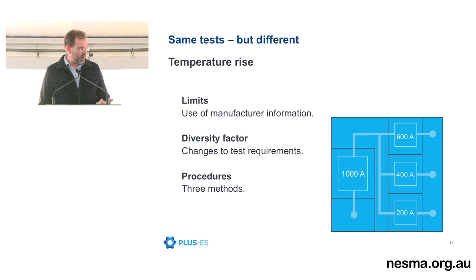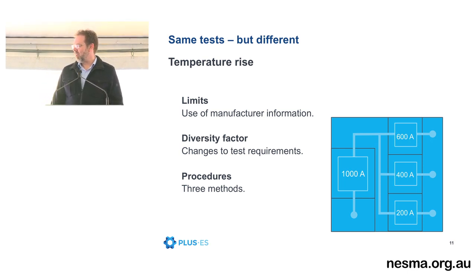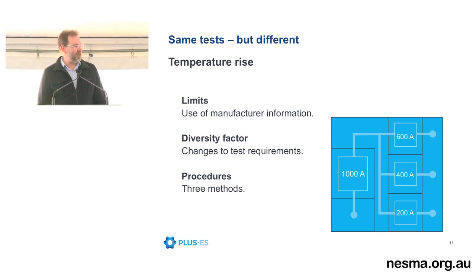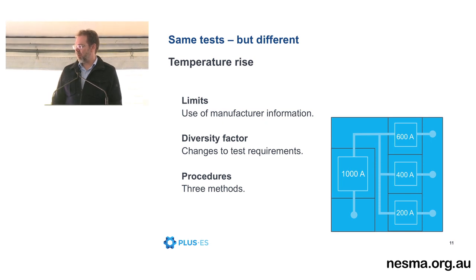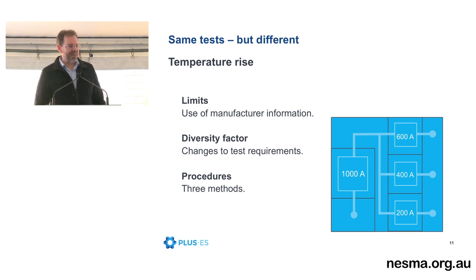So all those things have a temperature rise limit. Now, Australia's added a couple of extra notes to the temperature rise table, which changes slightly the flavour of how you interpret those limits, and probably the one that we would think about most is the temperature rise limit on a circuit breaker terminal, especially where that terminal doesn't form the connections for the external conductors. So a common scenario might be a Form 4B board where you have some bus bar leaving the functional unit, the terminals. So you know that you're going to have a piece of copper bus bar connected to that outgoing unit. Because you know that you're going to have a piece of copper there, you don't have to worry about sticking to the 70k limit for external conductors. But now the question is, well, what is the limit that you put on those terminals?